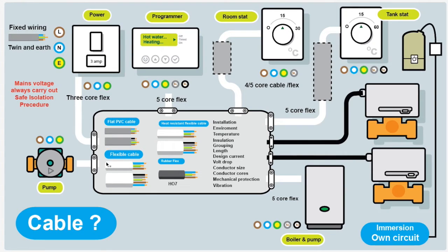So we can run our cable, cable clamped at both ends so it's nicely installed. It's easy to use. We also use flex as well because there's a slight bit of vibration in these heating circuits. We've got this pump which is turning around all the time. It's just a slight vibration. Over months and years that could loosen solid copper conductors like you get in twin and earth. So we use flex cable.